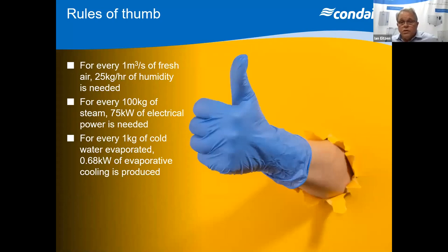From those conversations, there are three rules of thumb as approximations we generally use: for every 1,000 litres per second of fresh air, the approximate humidity requirement is 25 kilograms per hour; for every 100 kilograms of steam, approximately 75 kilowatts of electrical power is needed; and for every one kilogram of cold water evaporated, you produce approximately 600 watts of evaporative cooling.